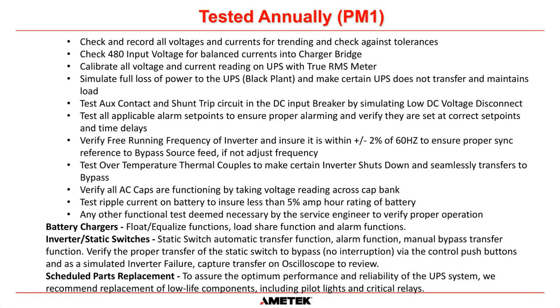We also test the auxiliary contacts and shunt trip circuits to the DC input breaker by simulating a low DC voltage disconnect. Near enough all UPS manufacturers have this threshold that we have to protect the batteries from being over discharged. For a 60 cell system, it's 105 volts DC. So there is a circuit within our UPS. If we lose AC power and the batteries are discharging, once it gets down to 105 volts, then the circuit says, okay, we need to protect the batteries, and it will trip the DC input breaker and shut the system down, basically.